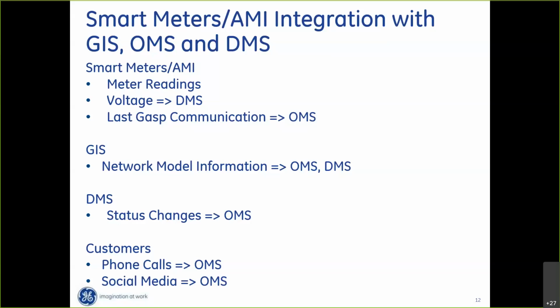So here we're showing not only the use of meter readings from smart meters, but also the voltage from certain meters at the ends of certain feeders that go into the network model and the distribution management system. We need that for Volt-VAR control. Also, when there's an outage, we get a last gasp communication from the smart meter, which we send directly into the outage management system.